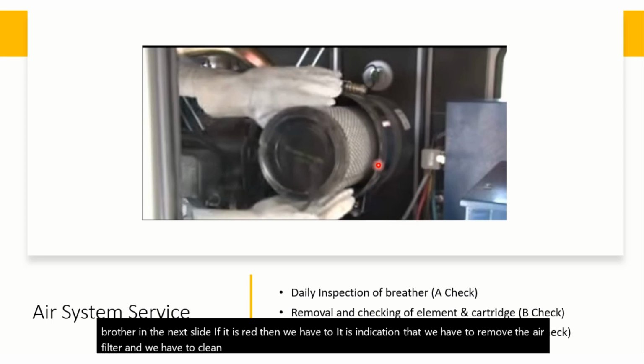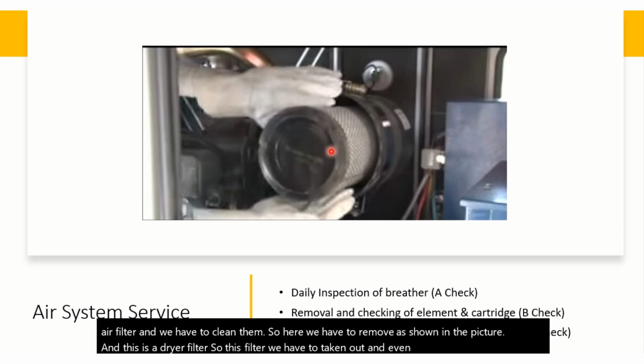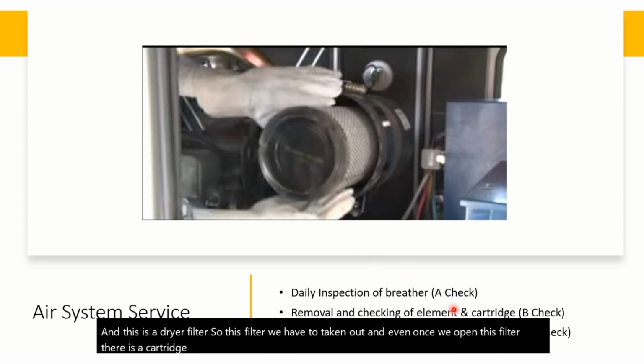So here we have to remove it as shown in the picture, and this is a dry air filter. This filter has to be taken out, and once we open it, there is a cartridge inside. This is a part of our B check, that every 250 hours or every 6 months we have to clean this air filter.